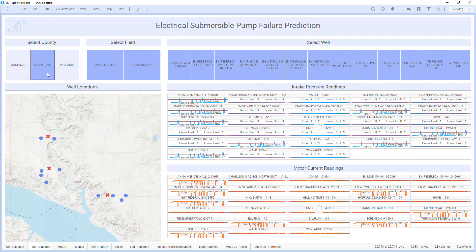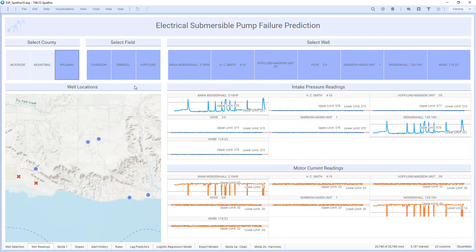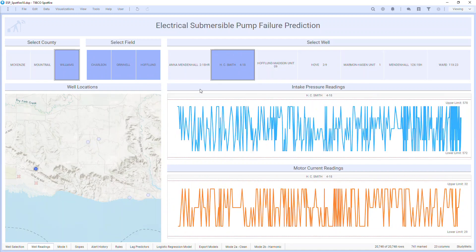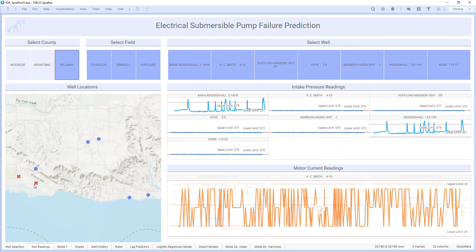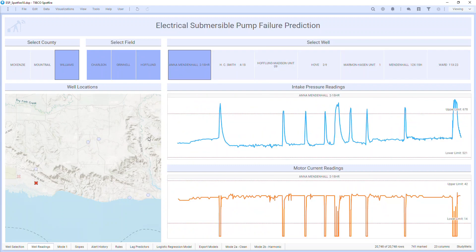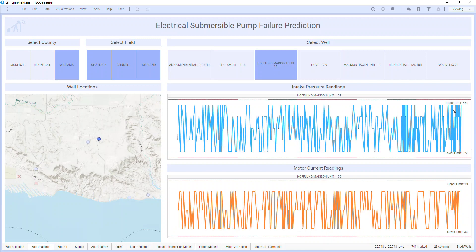On this page, I can drill into more details. I can explore wells by county or field, or even select individual wells. Selecting this well with failures from the map, I see a zoomed view of the intake pressure and motor current, both of which have those same spikes in the signal. I have these red dotted lines showing upper and lower control limits, and I see a pretty wide range here of 100 kilopascals for pressure and about 30 amps for current. Comparatively, the wells without failures have much narrower ranges for the control limits, indicating the submersible pumps have pretty steady operation.